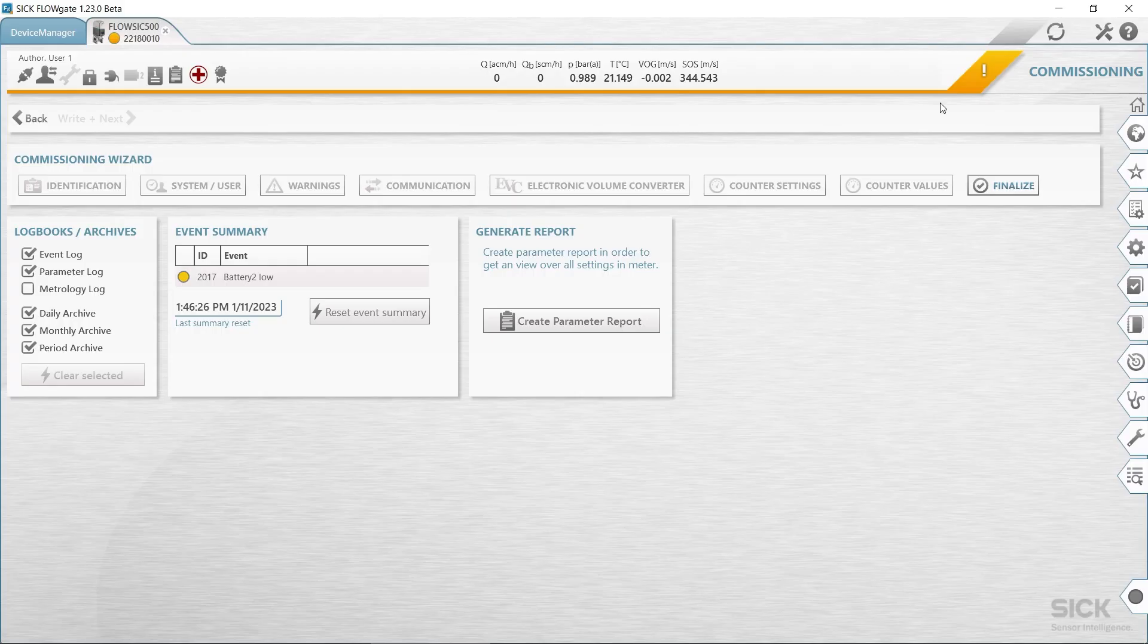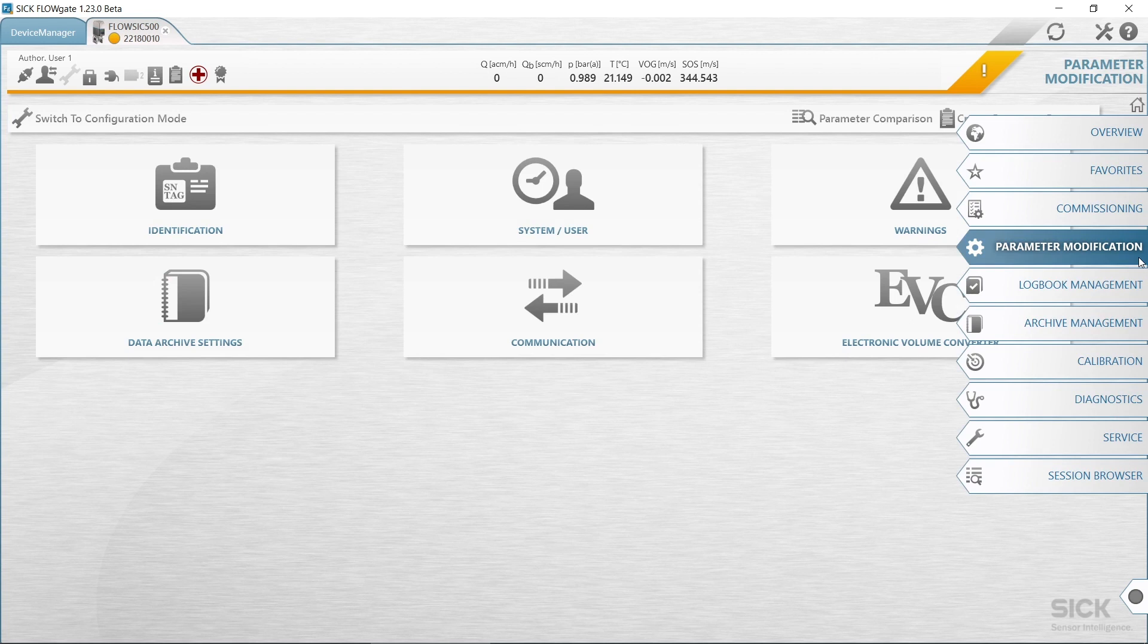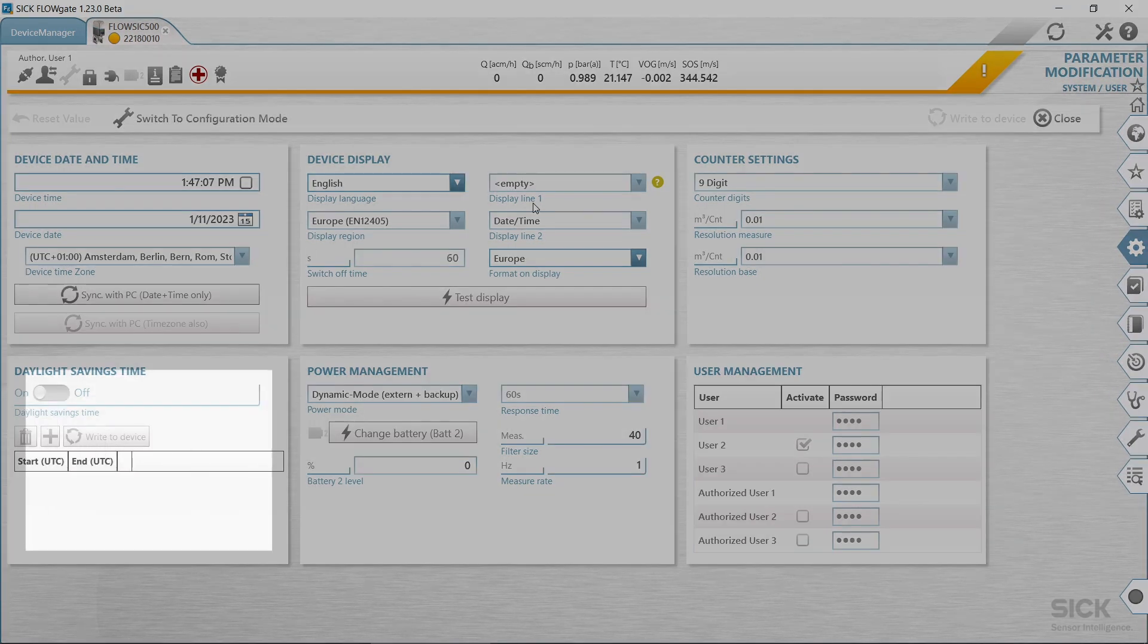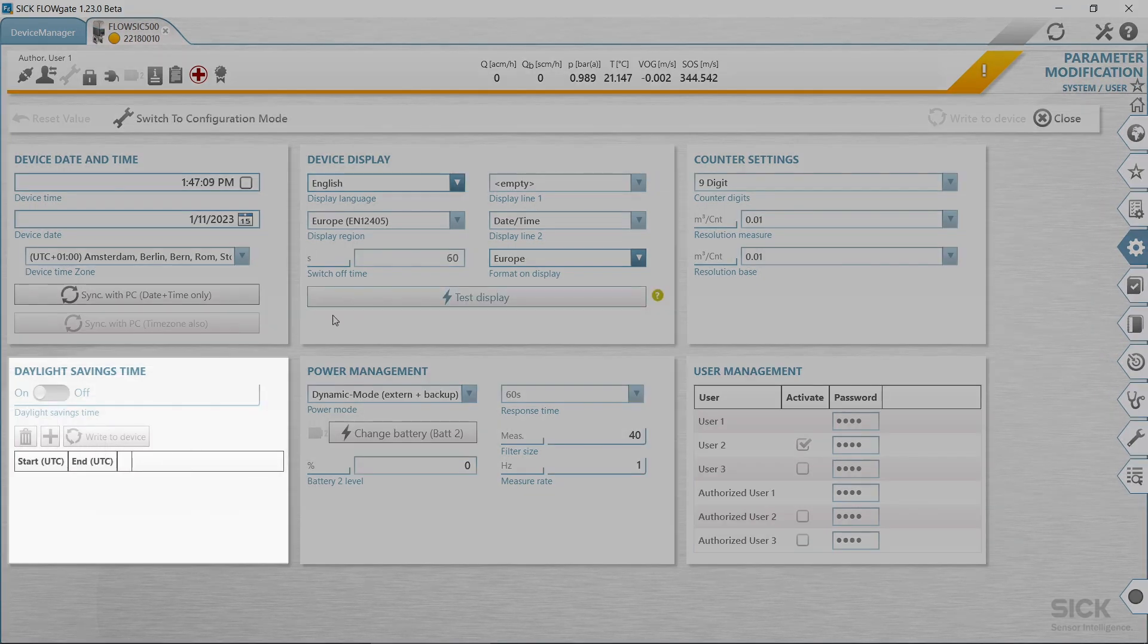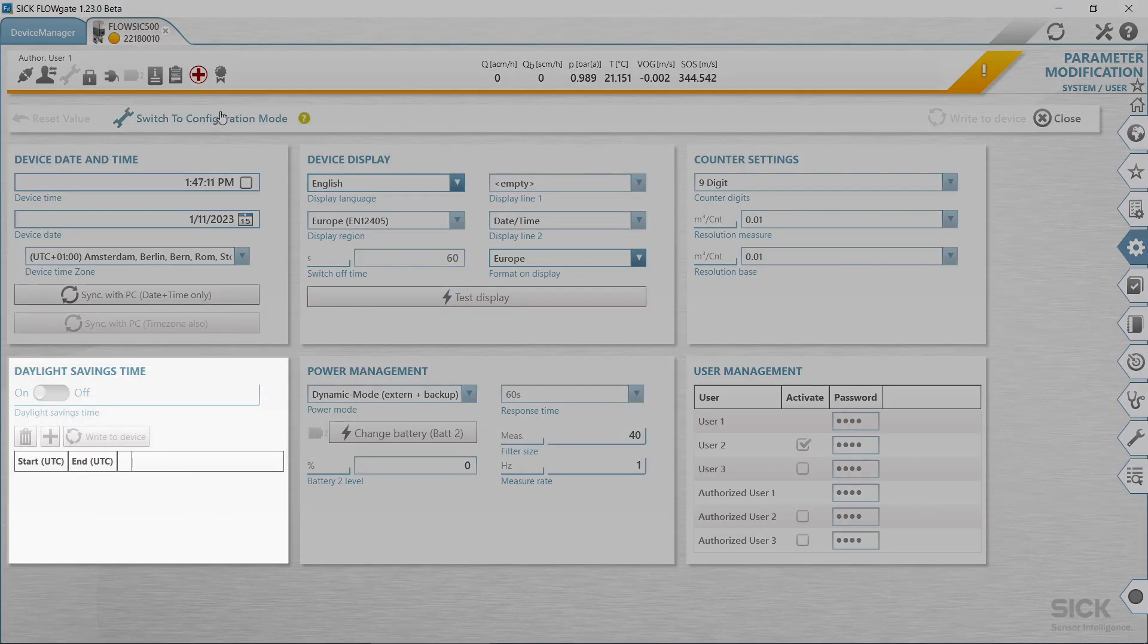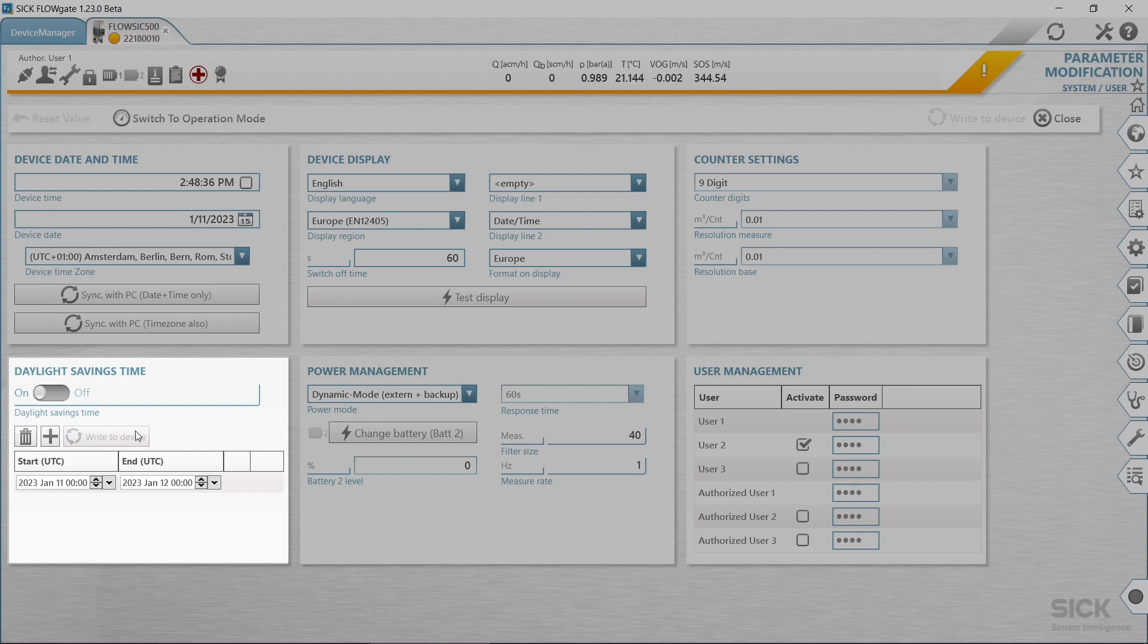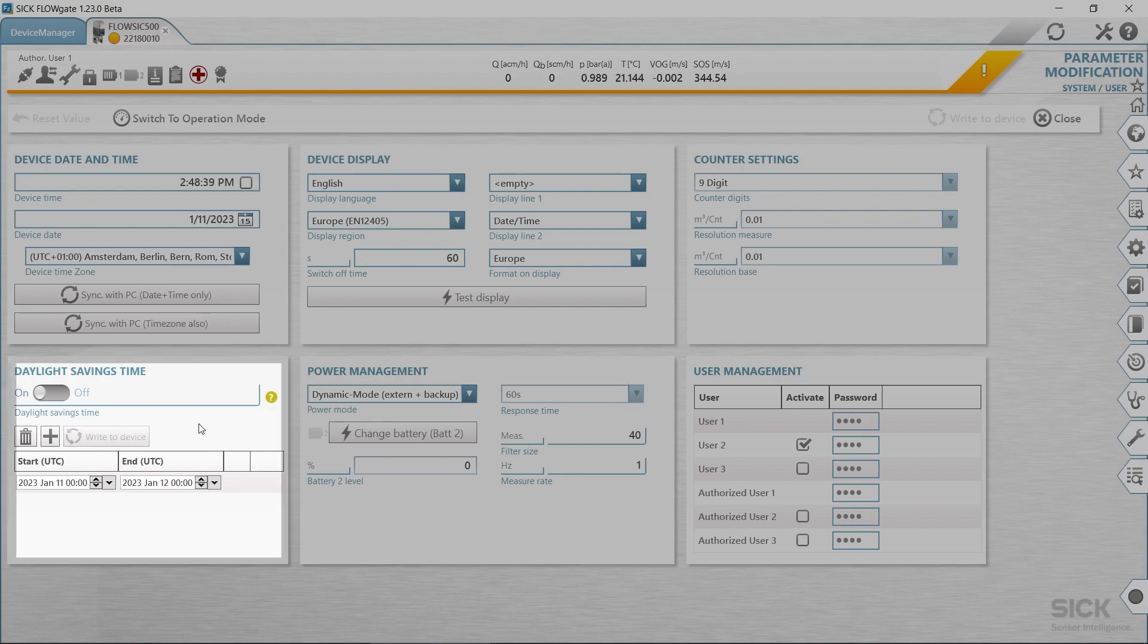After commissioning, we can activate and configure the daylight saving time. To activate and configure the daylight saving time, open the tile system user in the parameter modification area. Activate the configuration mode and activate the daylight saving time. Next, click on plus to enter a new time period for daylight saving time. Set the start of the daylight saving time. Date can also be entered by using the keyboard. Then set the end of the daylight saving time. Click write to device to write the daylight saving time to the FlowSIC 500. Enter further time periods when desired. Daylight saving time start and end can be configured for up to 10 years in advance.